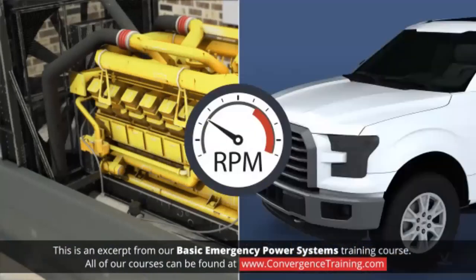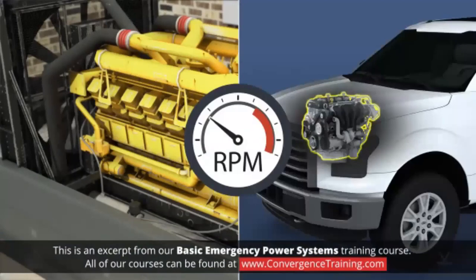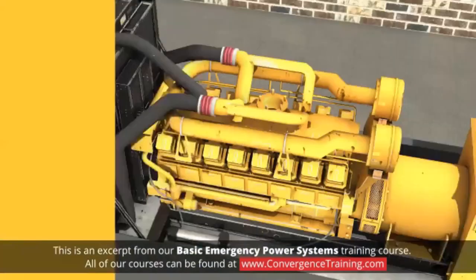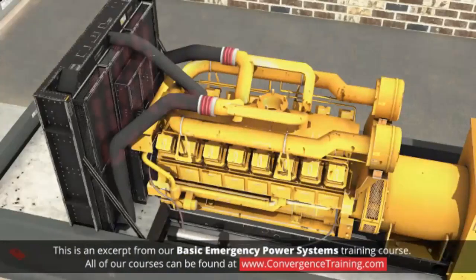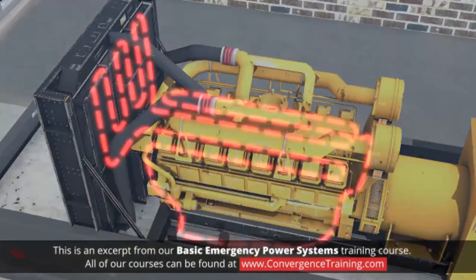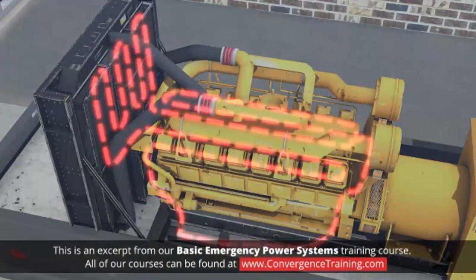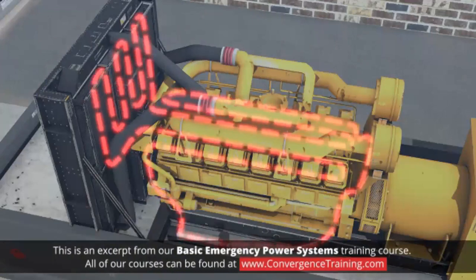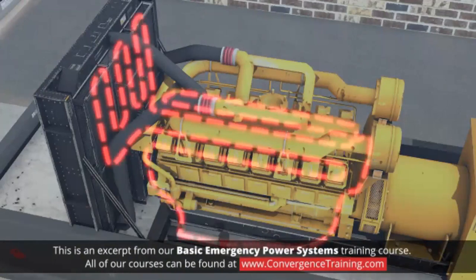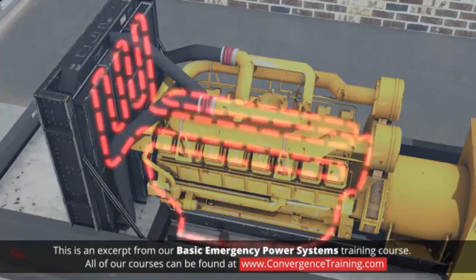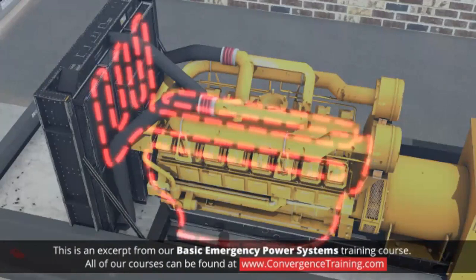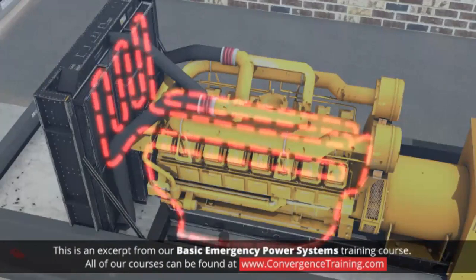Your typical automobile engine wouldn't last long if, when started cold, it was revved up to a high RPM right away, and this procedure was repeated every few days. To prolong the engine life in a generator, the block heater is used to keep the engine warm, but even more important, this keeps the engine lubricating oil at a free-flowing temperature, allowing it to circulate properly as soon as the engine is started, thereby facilitating quicker starting of the engine and maximizing engine life.